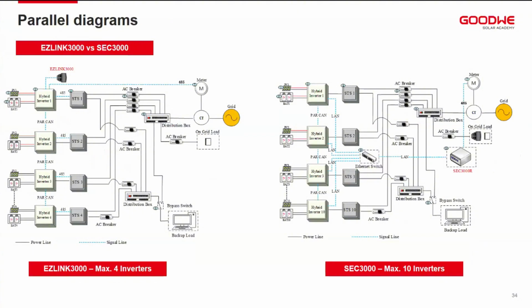Now those are single basis, but then the system is scalable. I mentioned the EZLINK. Now the EZLINK 3000, you can use it to scale up to 4 pieces of the ET series, 40 or 50 kilowatts. Each inverter connecting to its own STS, but because you're using the EZLINK, the inverter that is plugged to the EZLINK becomes the master and the rest become slaves to that inverter. So they report to that inverter. Similarly, the master inverter is the one that will monitor the grid incoming line that is connecting to the smart meter. So a single smart meter, a single inverter, a single EZLINK, those are the masters. Then the rest will be reporting to the master, the remaining 3 or 2 reporting to the master inverter.